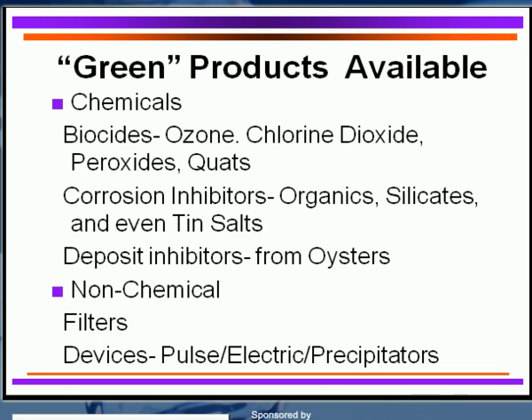For deposit control, we even get inspiration from oysters. Polymers utilized by oysters actually control their scale formation. The oyster's shell is calcium carbonate — that's scale. If the oyster continued to build that scale, it would eventually close up entirely, so it has a way of stopping it. We have learned to utilize that same mechanism in cooling water systems. Polyaspartic acid is what's used there — a very interesting approach. Non-chemical devices and filters can also be utilized to protect your system and stay green.